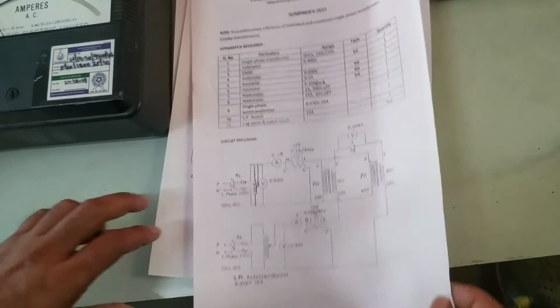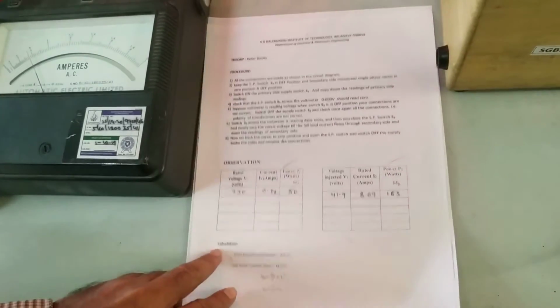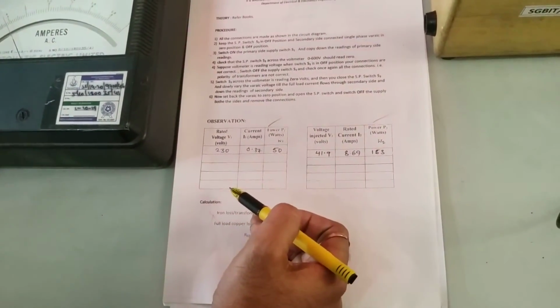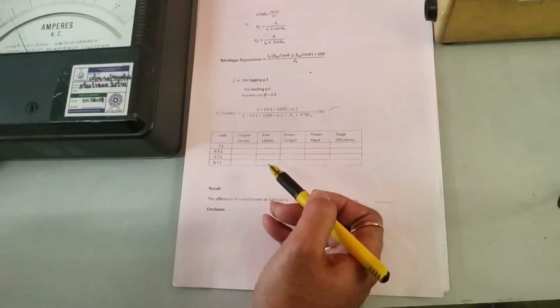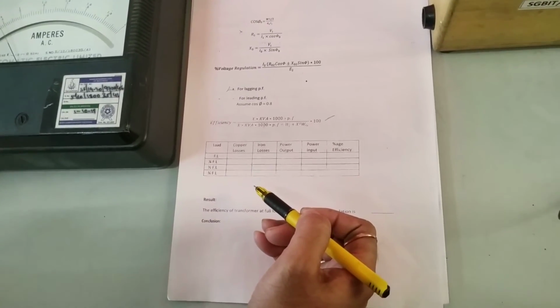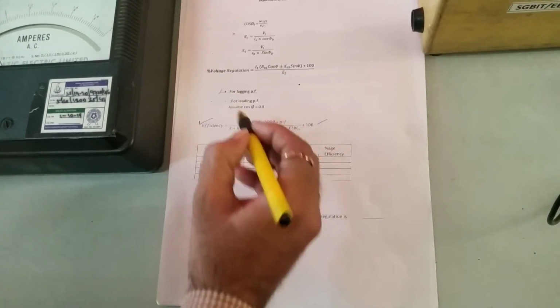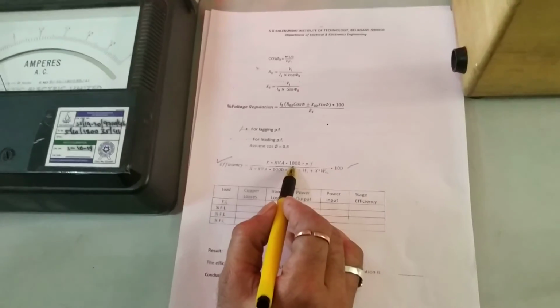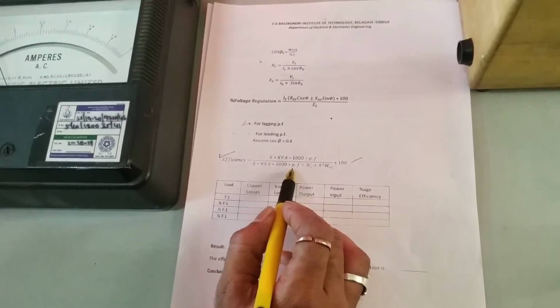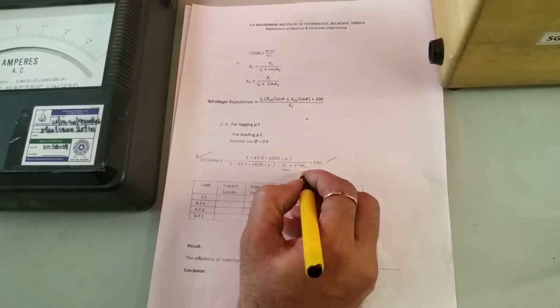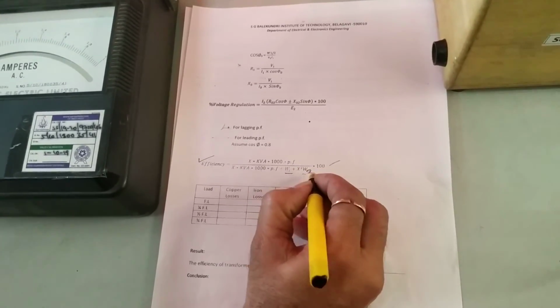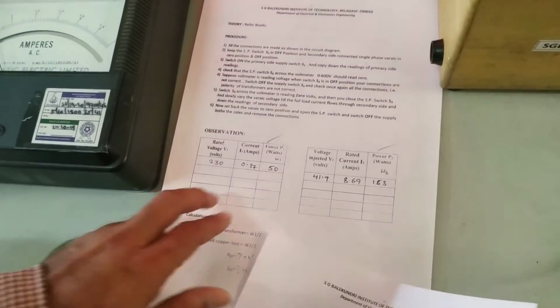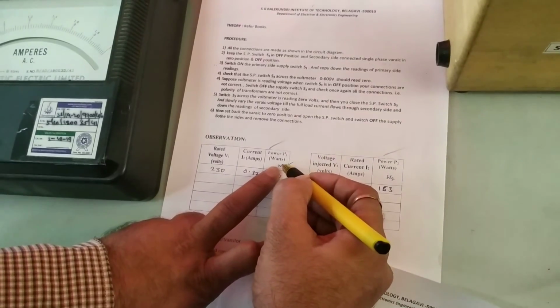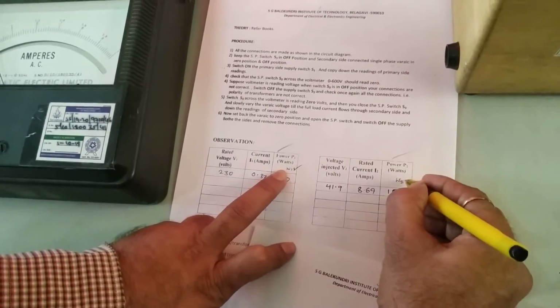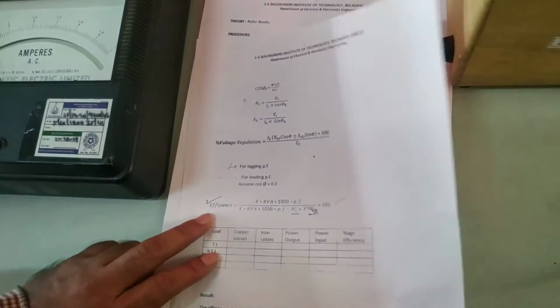So like this we need to conduct the Sumpner test on two similar transformers, and we need to take the readings, and finally we can calculate the efficiency of a single transformer, that is the individual transformer, or we can also calculate the efficiency of the combined transformer. With the help of this formula we can calculate efficiency: x into kVA into 1000 into power factor divided by x into kVA into 1000 into power factor plus W1 plus W2. These two values can be taken from this table. W1 is nothing but the first wattmeter reading, and W2 is the second wattmeter reading. Those can be taken and put here.